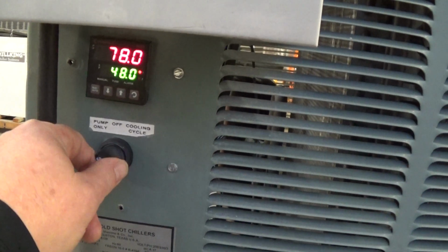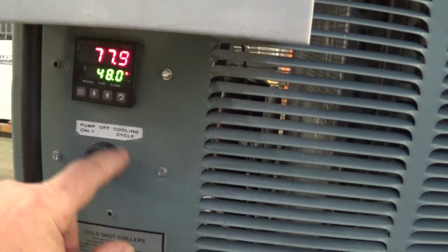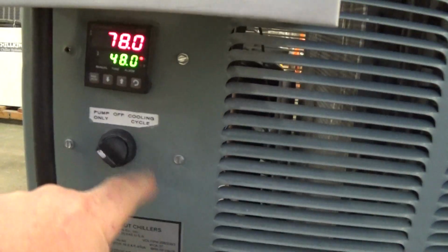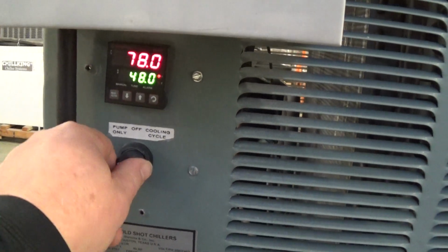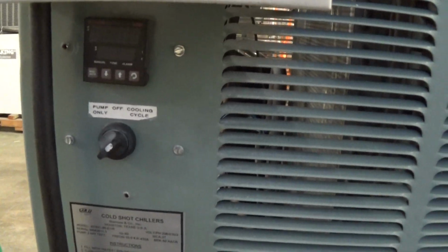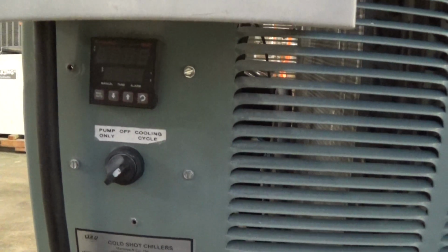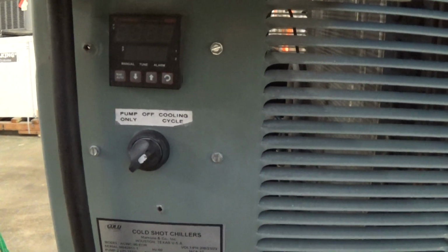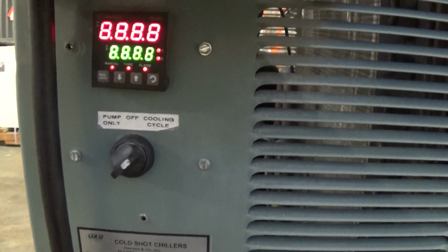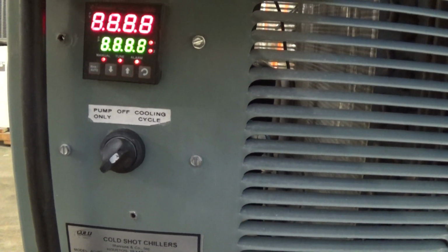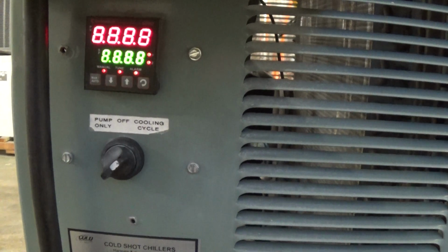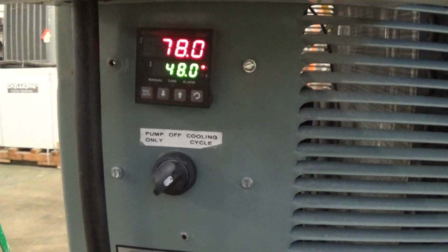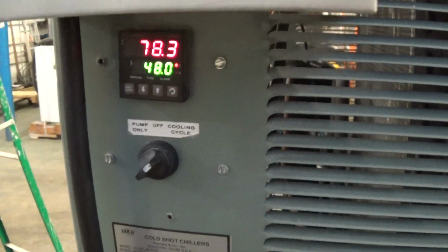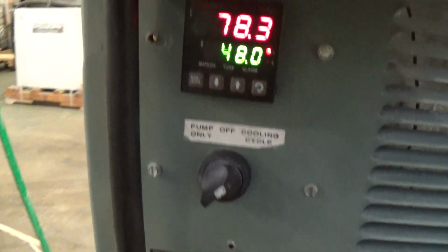Then we're going to change it to our cooling cycle, not just pump only. When you're on cooling cycle, the pump will continue to run full time. So when you do that, it's going to go through that little reset of the controller again. But that set point should be embedded in memory. Let's see how that comes up. Yep. And so you just heard the compressor turn on.